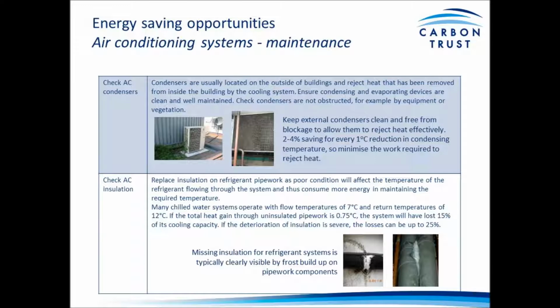So if it's having to increase that condensing temperature, then it has to work harder and use more energy. So clean and remove all blockages where you can, internally and externally. Some examples there of blockages that we commonly see with external condensers, with plant or other debris outside in plant areas.